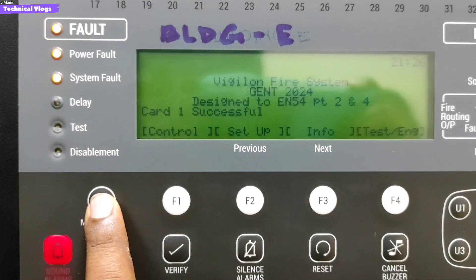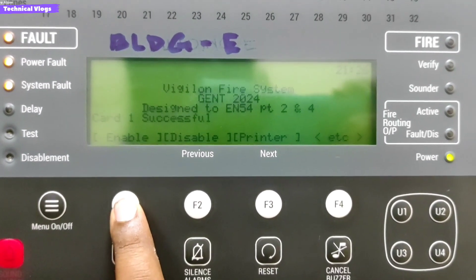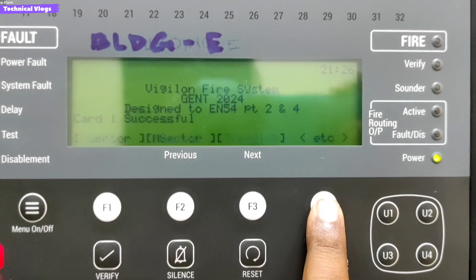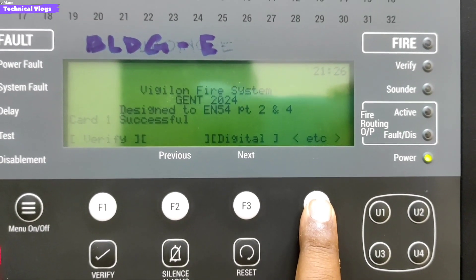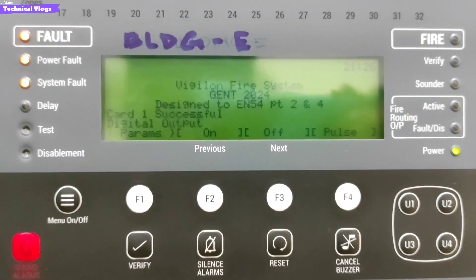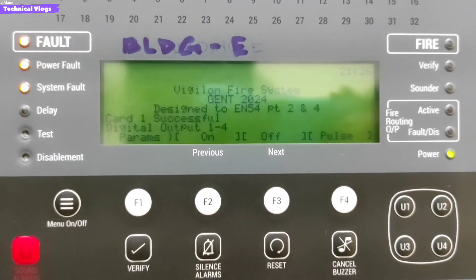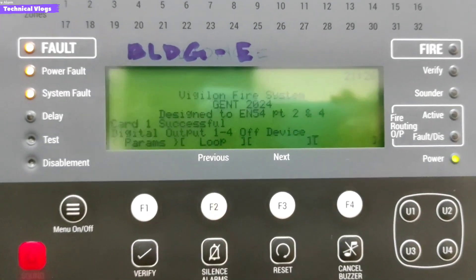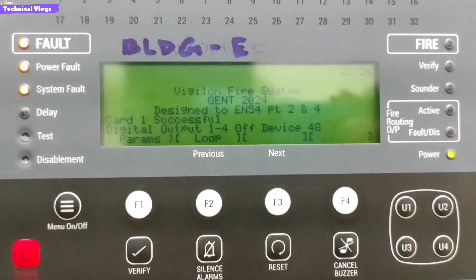Repeat the same procedure to exit from digital operation. Press the menu button and go to the control option. Then go to etc, then again to etc, and etc. Then you get the digital option. Put 1 to 4 in digital output and go to the off option. Put device number 48 and loop number 1, and press enter.